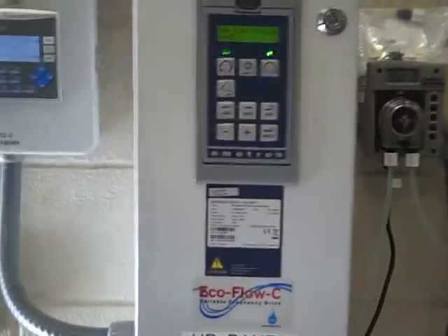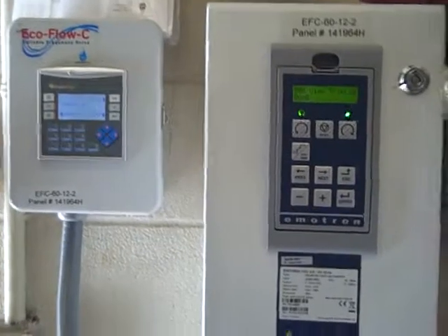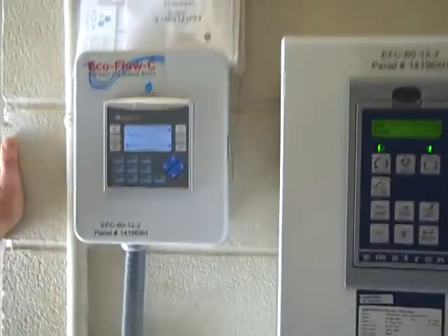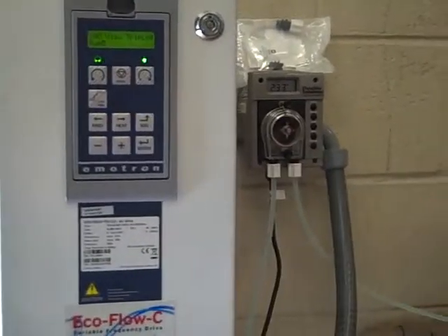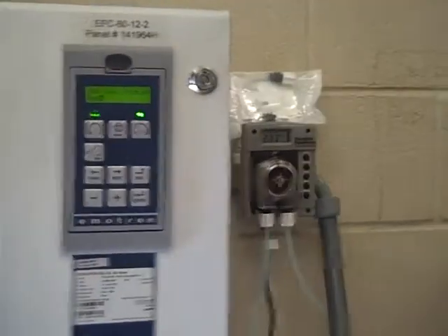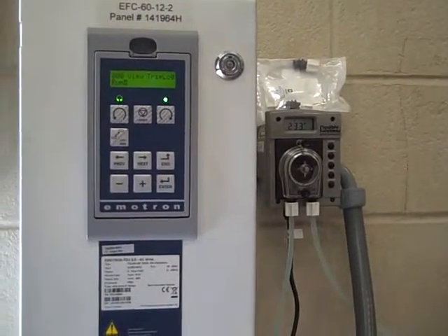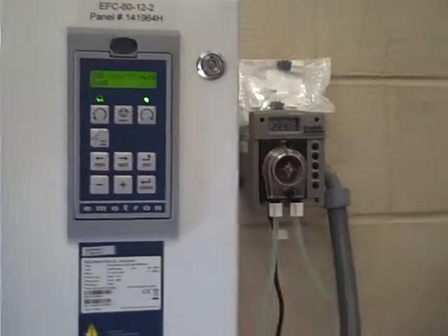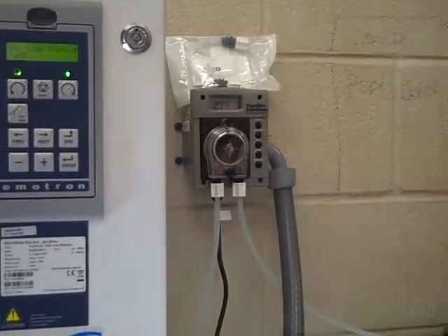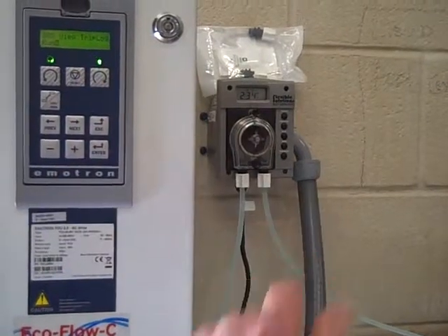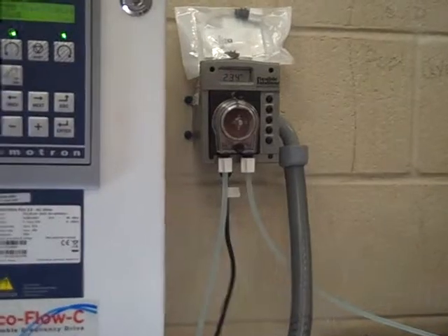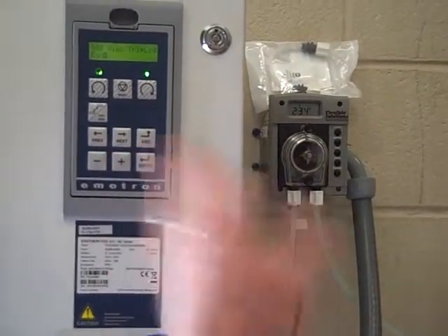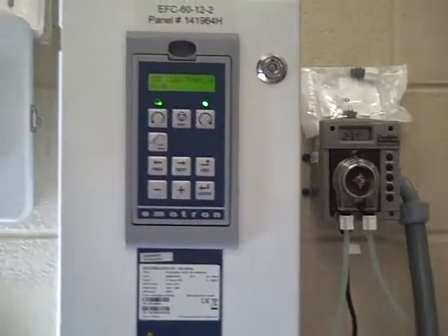And whatever this error code is, you can look it up in the manual, and it'll tell you. The one you see most often is undercurrent, which means you've got power fluctuation, or overcurrent, just power fluctuation. The drive will shut itself off. It's set up now so it'll automatically restart, okay? But if you get an I square T error, that's your alert that there's a mechanical failure coming up, whether it's bearing or impeller wear. So if you have an error code, just give me a call and I'll walk you through it.